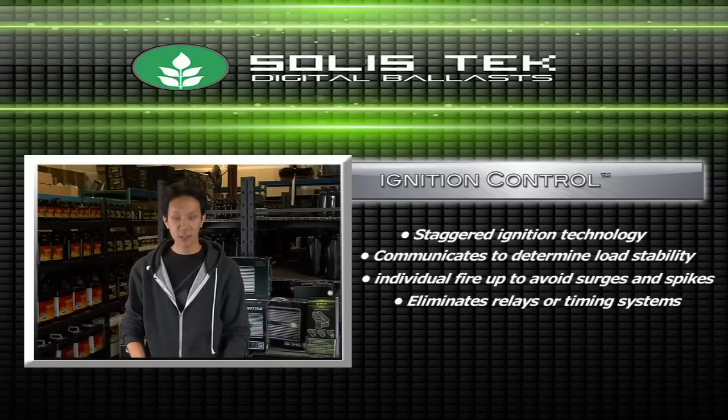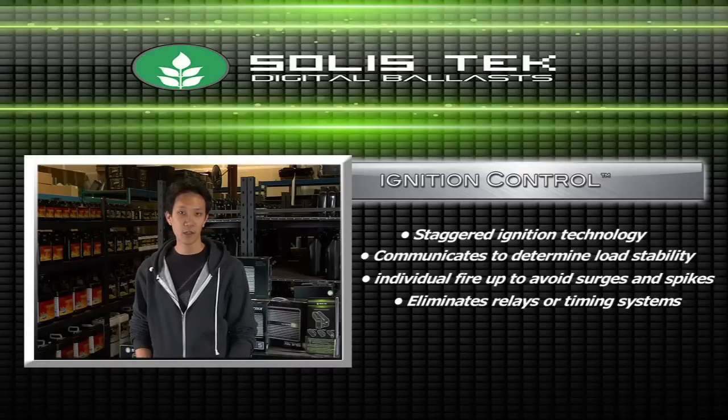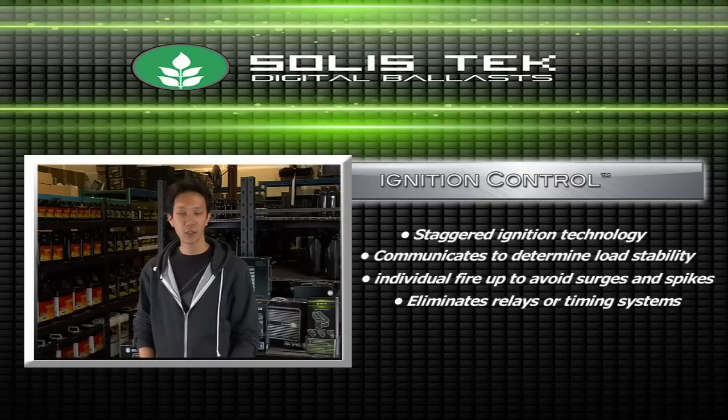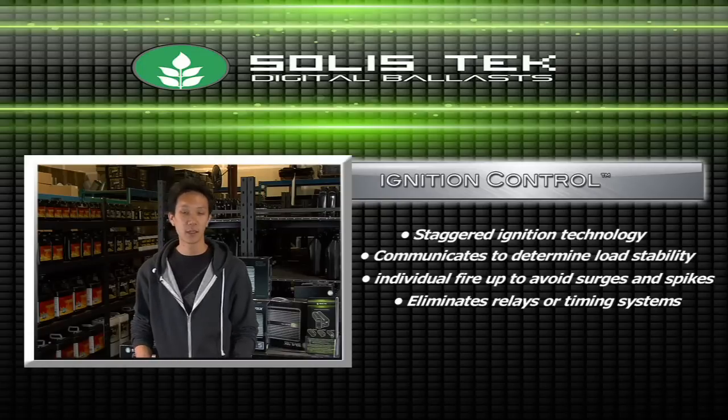Solis Tek is the founder of ignition control technology — that's our one-at-a-time staggered lamp ignition technology. Our ballasts are actually able to detect load stability within the line current, and the ballasts will fire and ignite as the load becomes the most stable. What this results in is a one-at-a-time staggered lamp ignition, thus decreasing the chances for spikes and lessening the chances of tripping your breakers.